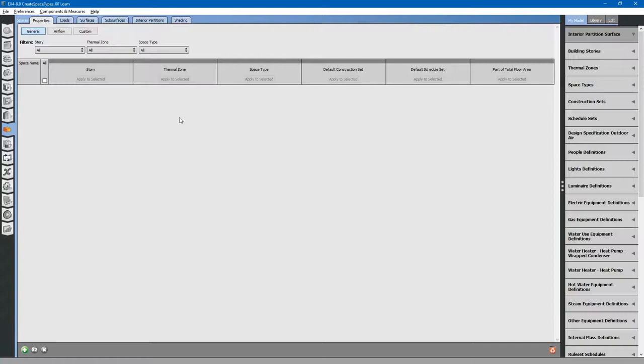You can apply very specific information to an individual space at this level. So if you have six classrooms and one of the classrooms has two extra people, or one has a lot more lighting, you can apply it at this level. This is the first place OpenStudio looks. All of the information under properties, loads, surfaces, shading, air flows - OpenStudio looks there first. If it cannot find that information, OpenStudio will then look at the Facilities tab.